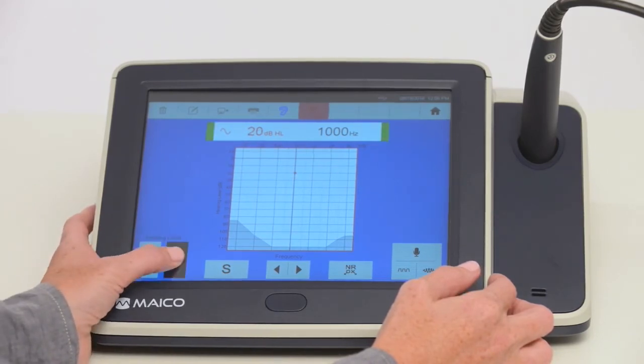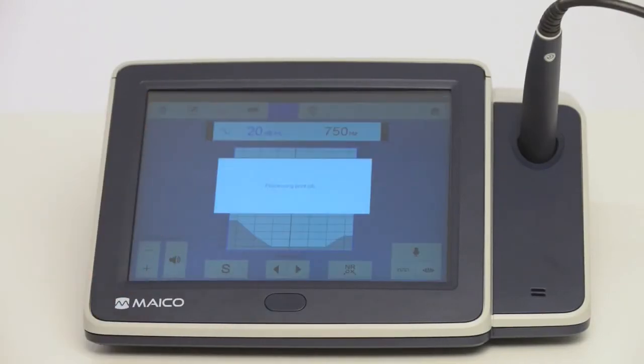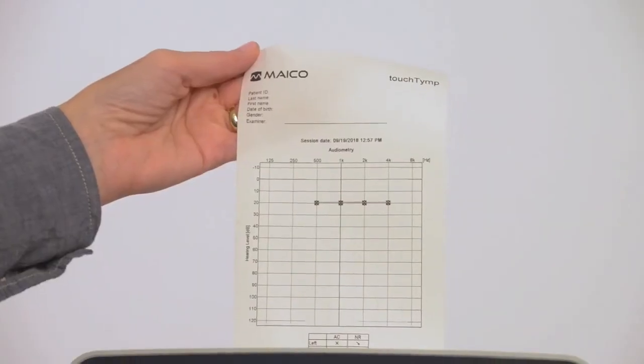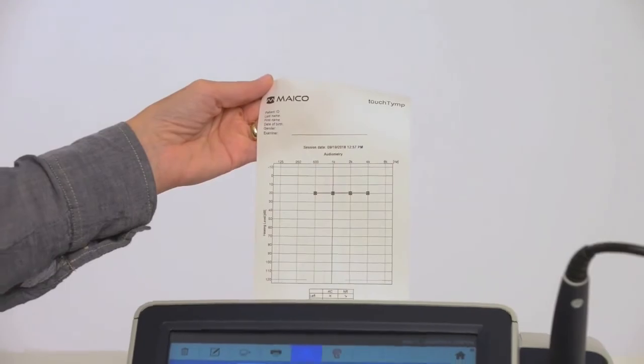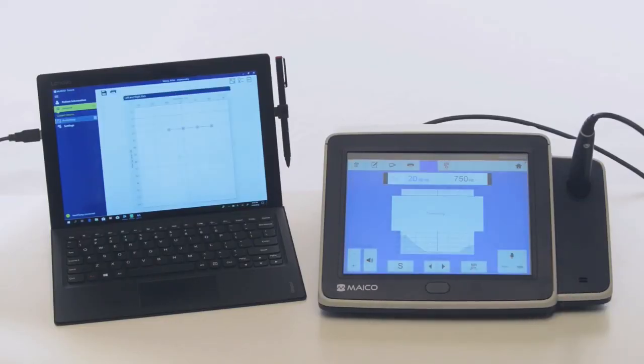Results can be stored on the device by pressing the S button. Final testing results can be printed by selecting the print button or transfer to a PC by pressing the transfer button. Transfer requires the TouchTimp be connected to a PC and the Maico software open.